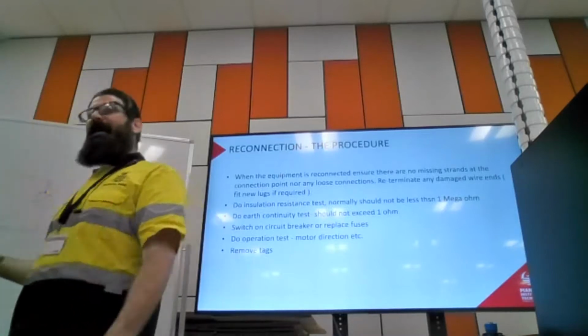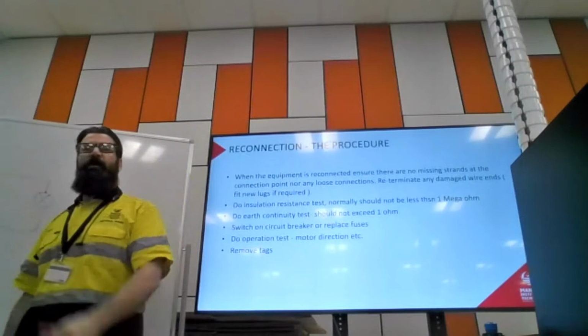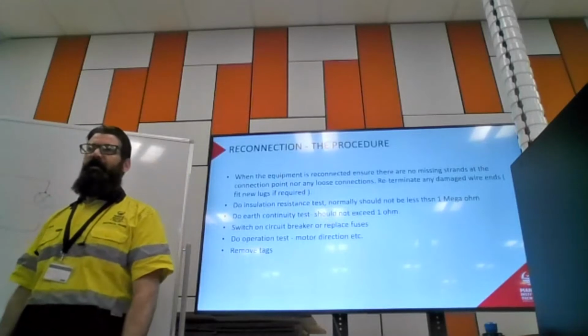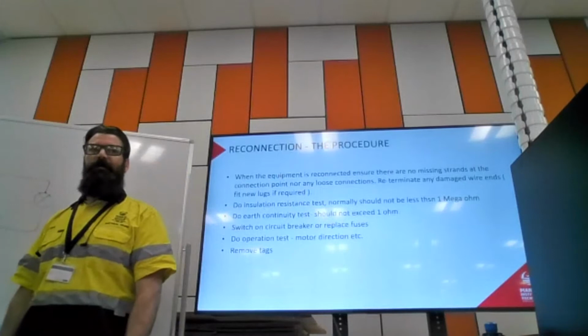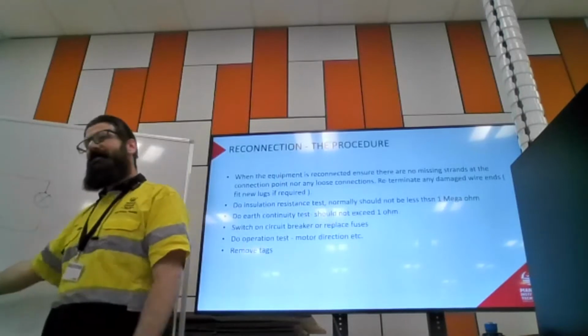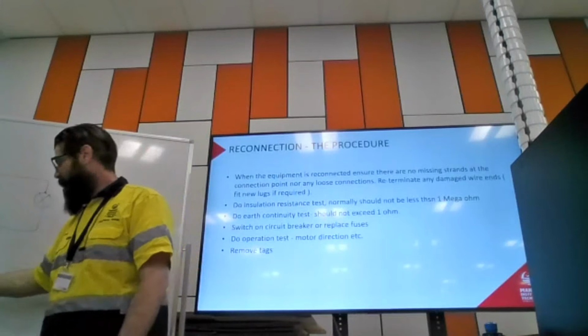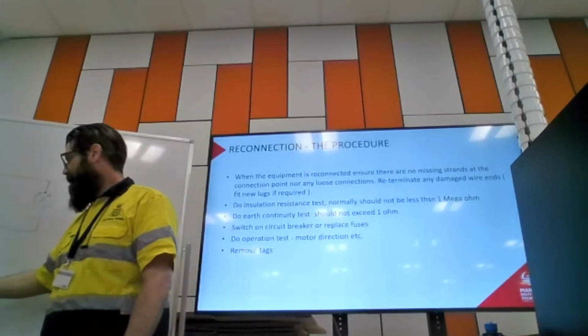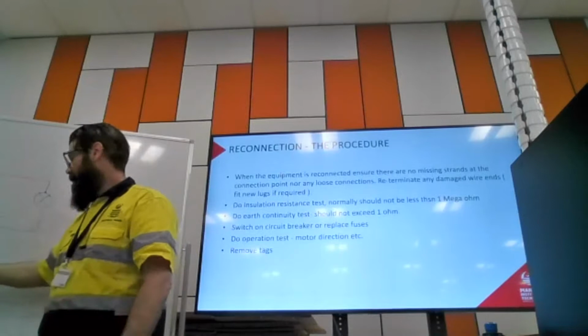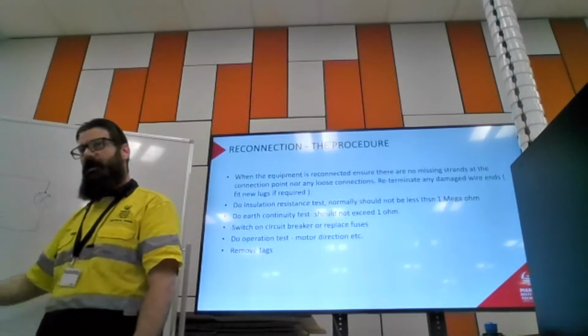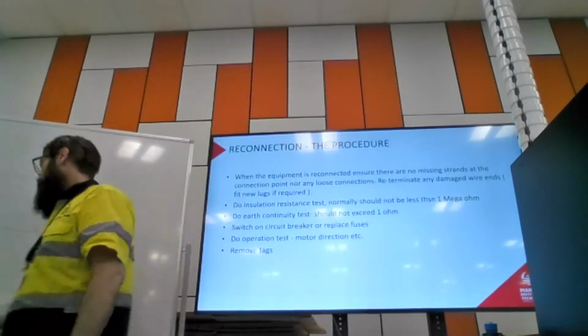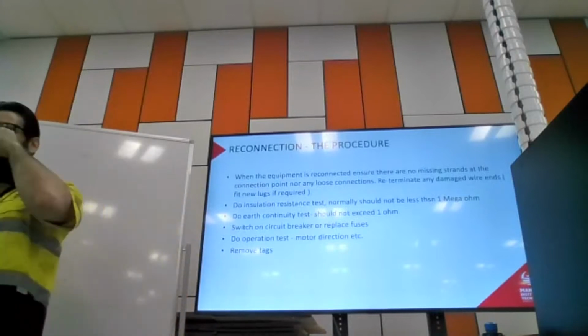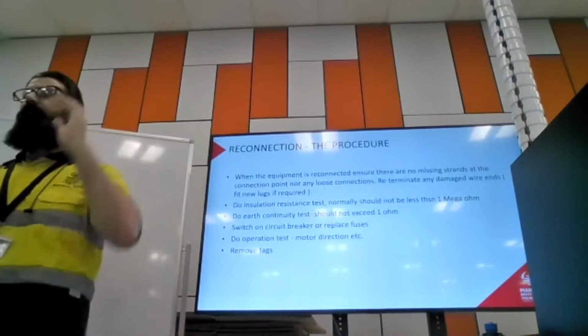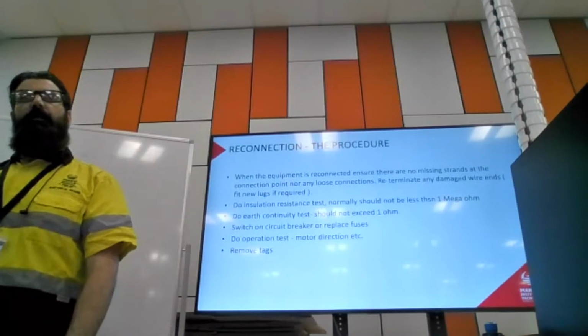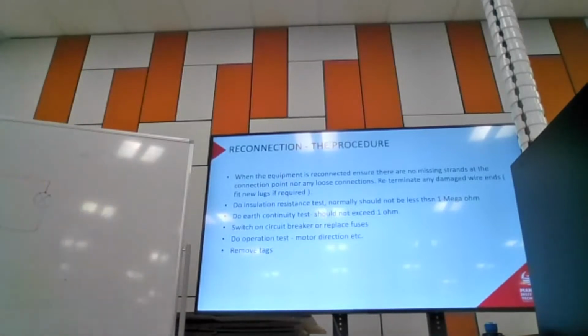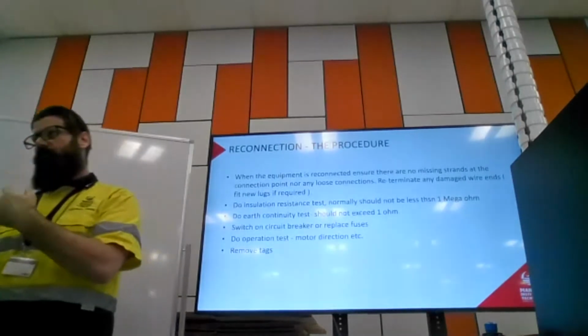But we can't use traditional insulation. I can't use rubber insulation, or PVC insulation. Why not? Because it'll melt. It's hot as hell. It's literally a red hot wire in the middle there. If I put any sort of PVC between that coil or that conductor and the outer sheath, which is earth, then it's just going to melt. It'll be completely hopeless. So our best insulation is magnesium oxide, that white chalky stuff. If you haven't seen that, I don't know if I kept that element. Oh, we'll have a look. We'll find something at some point. Because it's really heat proof. It's a fairly good insulator and it's really heat proof.